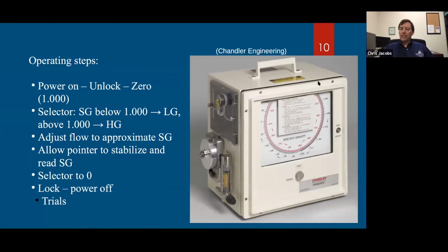Once your inverter has been operating in a stable condition, you will plug your AC into your inverter. You'll then unlock the machine. As I mentioned, you unlock it from this position over here. And what happens is the needle will start drifting down towards 1.00.